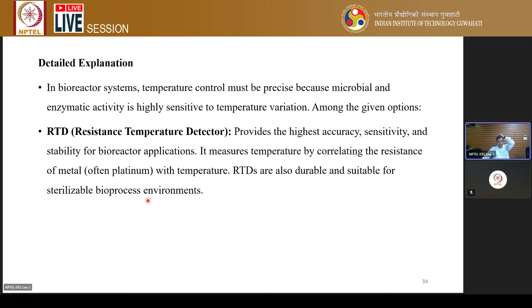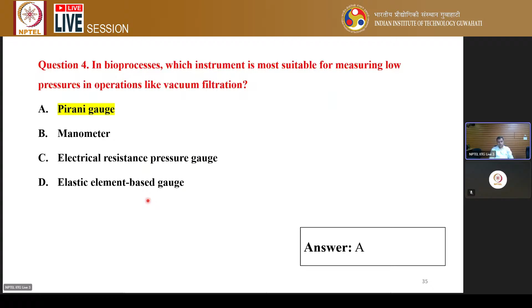As you need to measure pressure: in bioprocessing, which instrument is most suitable for measuring low pressure? We have discussed high, moderate, and low pressure, as in operations like vacuum filtration. The manometer, electric resistance pressure gauge, and elastic element-based gauges like the Bourdon tube pressure gauge typically measure high pressure. Only the Pirani gauge can measure low pressure, particularly vacuum pressure, for measurements less than 1 millibar.